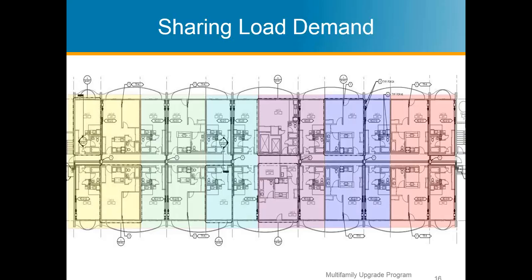through the compressors, through the variable speed drives, it adds longevity to the system, the operating of it. So if you're operating right-sized equipment, the system should last longer. If you're operating a larger piece of equipment on a space that does not need all of that load or that capacity, then it's just going to keep kicking on and kicking off, and things start breaking down because it's just oversized.